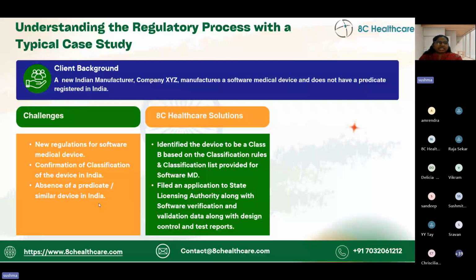Depending on the class B classification, we filed an application to the state licensing authority. Since it is a new device, we submitted all the requisite software verification and validation data along with the design control and the test reports. Since we submitted the requisite data to establish the safety and reliability of the device, we submitted the application to the state licensing authority.